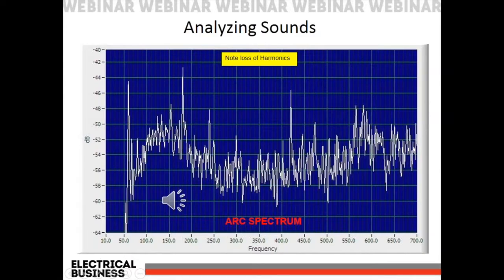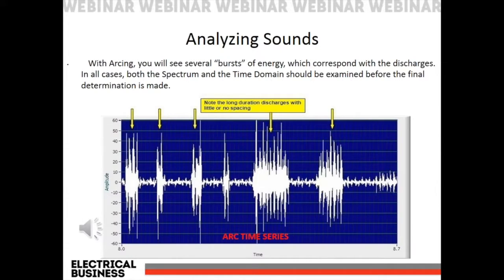As we go forward into the time series, now we start to really understand why this is arcing, because now these events are very long and drawn out. They're very violent stops and starts that occur, where with tracking, what we had was a building of intensity and then discharge, a build of intensity then discharge. These become, in the arcing realm, very abrupt and very violent stops and starts. And therefore, by looking at the time series, we can see the larger events that are occurring, the lack of ionization in between the events as well, and we clearly hear the discharges taking place throughout the sound file as well as in the time series here.